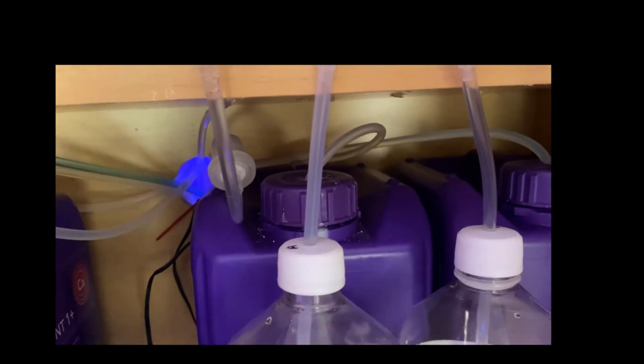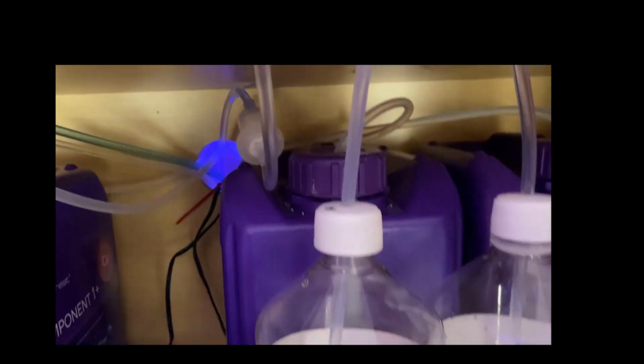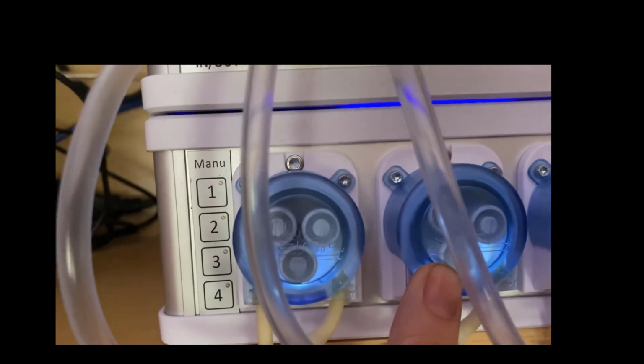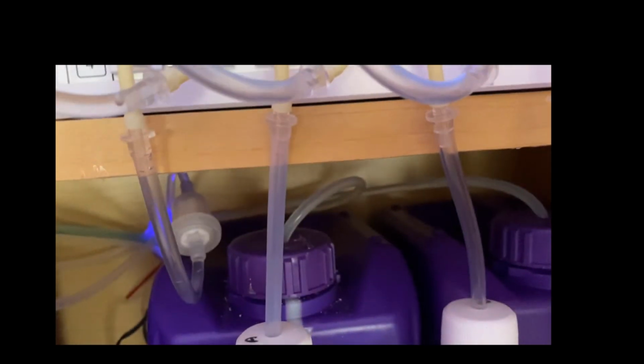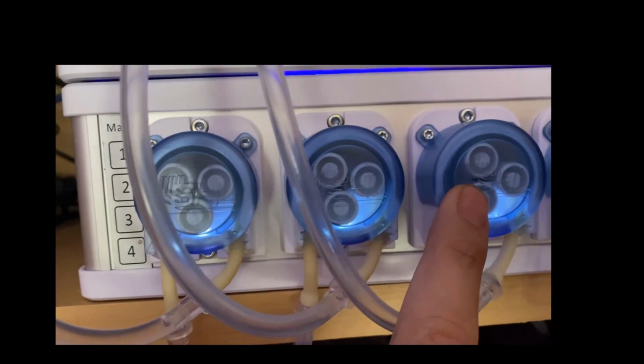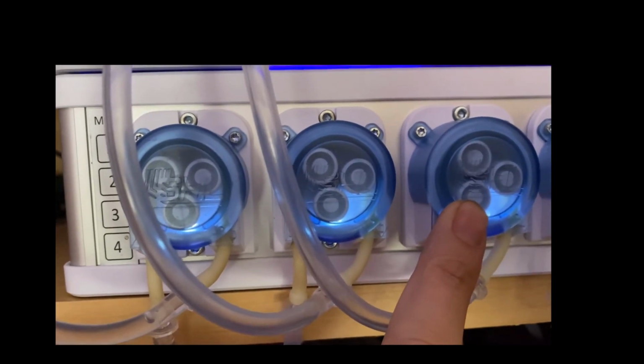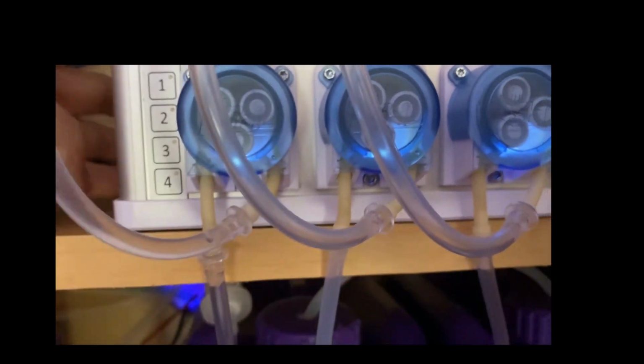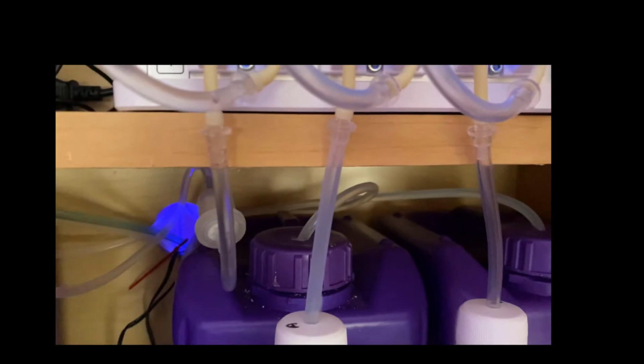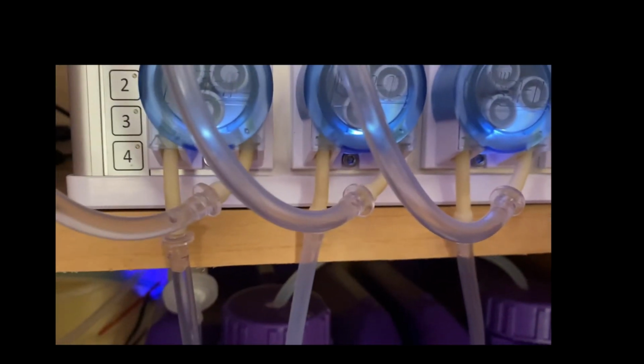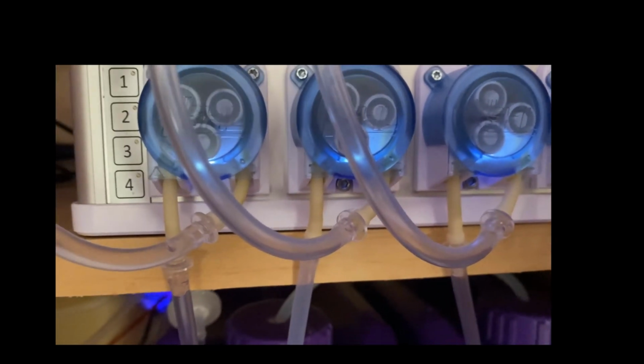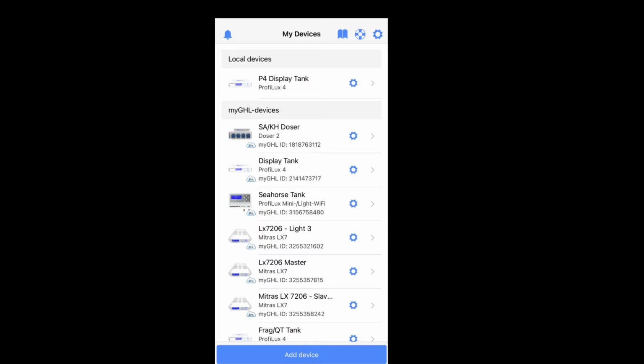With the water supply now installed to the doser, we can continue with the reference A being connected to the reference A dosing pump, and the reference B solution being fed to the reference B solution pump. Now with the water supply line, the reference A and the reference B solutions installed, the last thing that needs to be done is the priming of all 3 pumps. With the priming of the 3 dosing pumps to the ion director complete, we can now continue and finish the setup of the ion director.